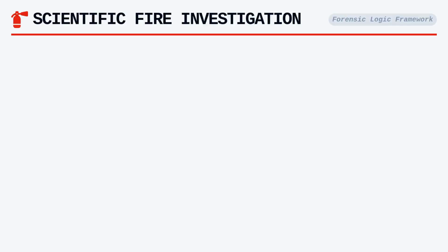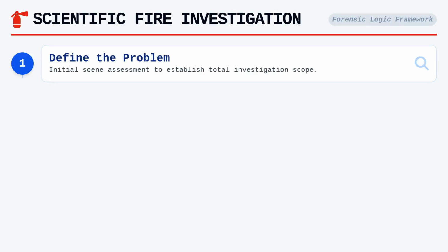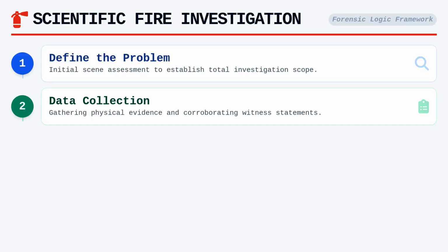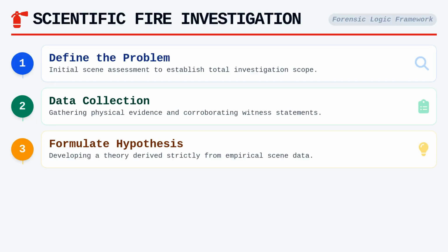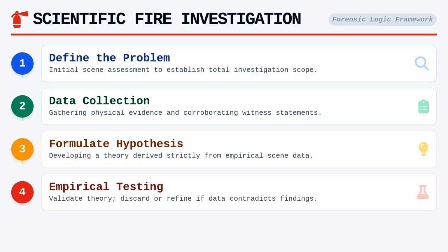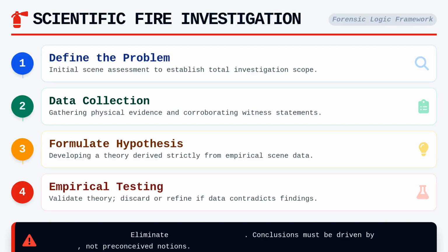Effective fire investigation requires a strict adherence to the scientific method, as a forensic analysis is only as reliable as the logical framework supporting it. We begin by defining the problem, which often involves an initial assessment of the scene to establish the scope of the investigation. Once the incident is defined, we move to data collection, which encompasses everything from physical evidence to witness statements. The critical step involves the formation of a hypothesis that must be tested against the empirical data gathered at the scene. If the data contradicts the hypothesis, we must discard or refine our theory, as the investigation must be driven by objective evidence rather than preconceived notions. This iterative process prevents cognitive biases like confirmation bias, which can lead even experienced investigators to settle on an incorrect origin or cause prematurely.